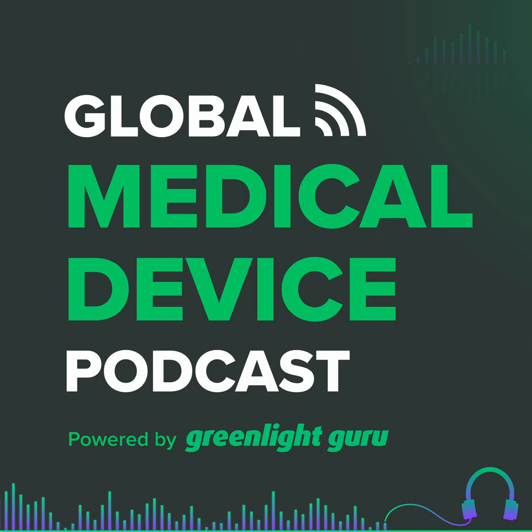It was great. And the FDA came back and said, well, have you considered when a patient is in this medical state? They are looking at it, as we were talking about before, from the patient perspective. When they were looking at the risk, and I should say I helped out a little bit, they did the majority of it, they took just a patient in the normal state that they expected the patient to be in. The FDA said, that's not good enough. We want to know what happens when the patient is in this state. They were working on a very high risk device, so patients in different critical states.